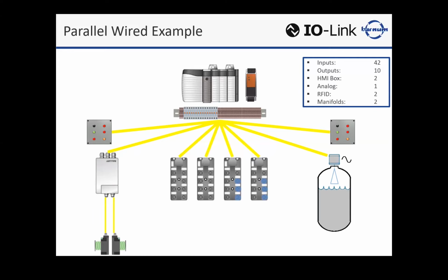All right. Lastly, we just add some manifolds. Yep. Valve manifolds. There's obviously motion on the machine. Throw up two of those with, I don't know, let's say 8 valves apiece. All right. Perfect. So this would be a conventional layout. You would agree? This is showing all the wires passing back to the terminal blocks. For any of your outputs, do you want to explain what we've got here? Yeah. So obviously inputs are all hardwired back to terminal blocks, then hardwired through swing arms back to the PLC cards.